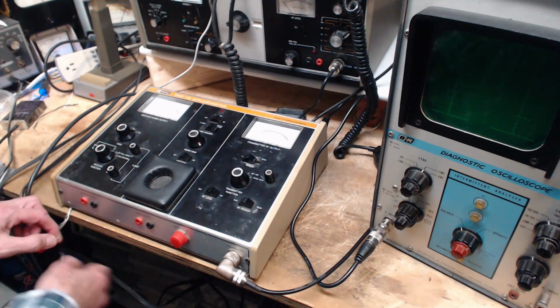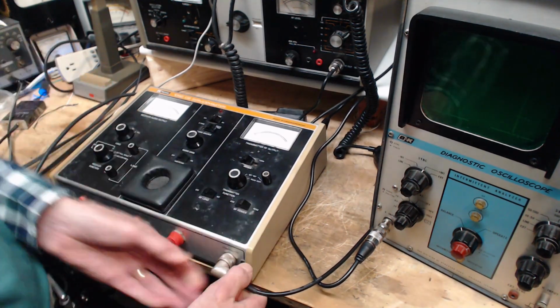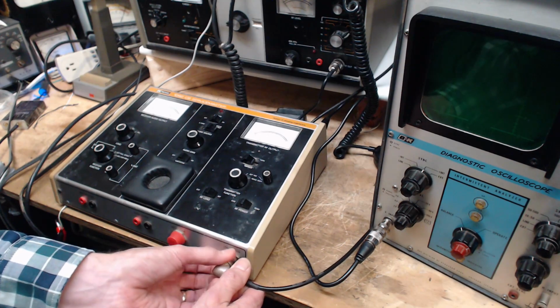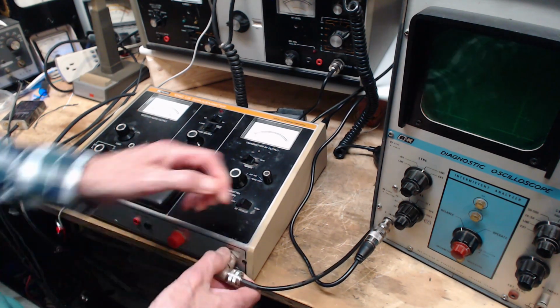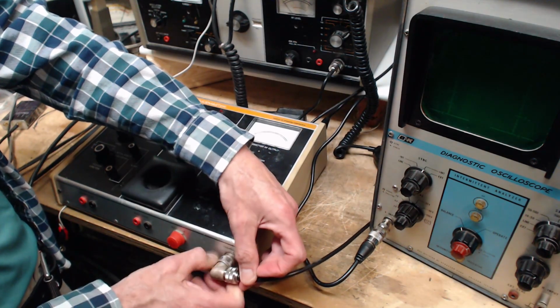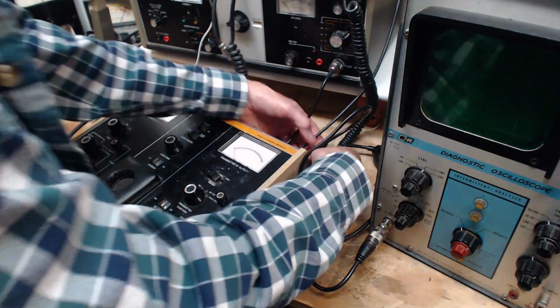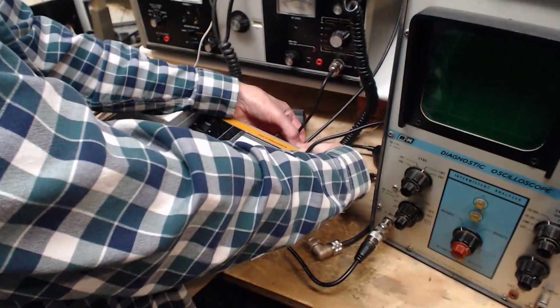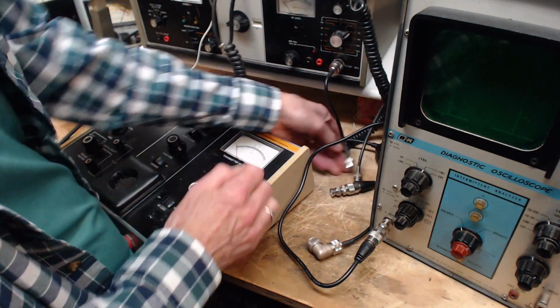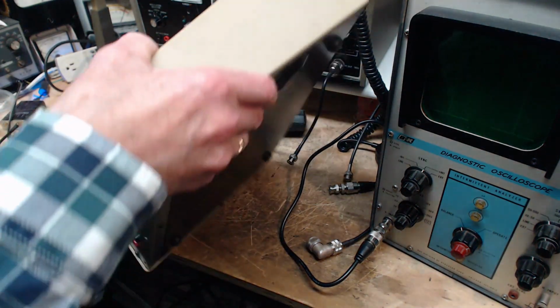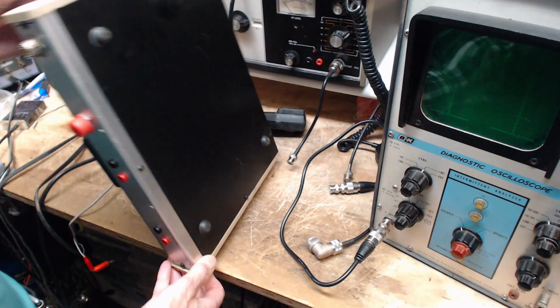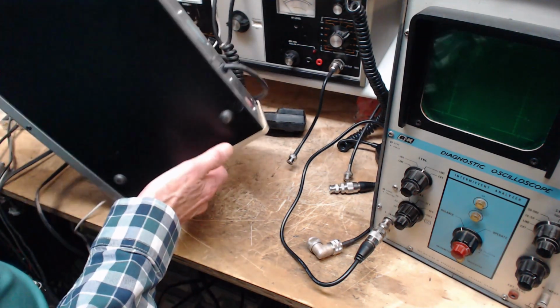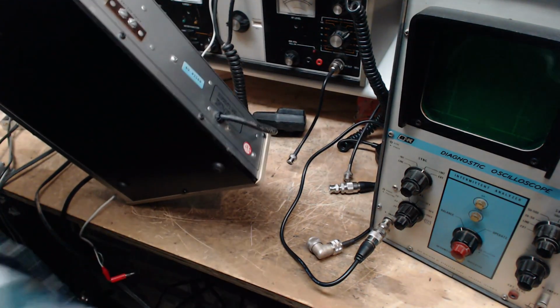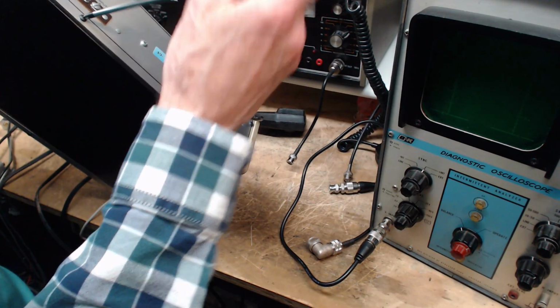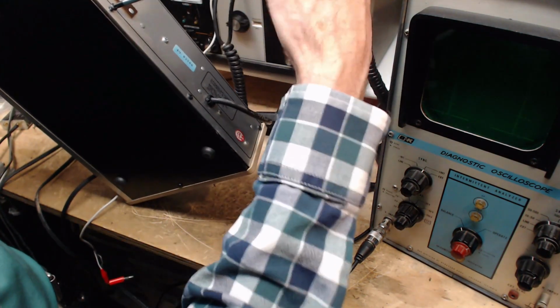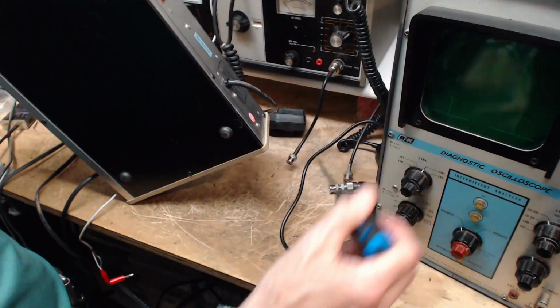Okay, 5 screws to remove. Disconnect these. Okay, power's off to everything. Let's see. 5 screws. 1, 2, 3, 4, 5. Okay. Somewhere in the manual it says all the calibration can be done by just removing this back panel and nothing more.